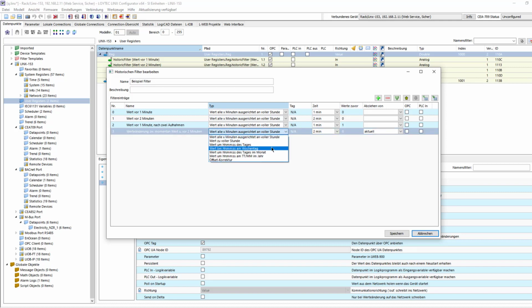Noteworthy is that if one has an energy consumption meter, then one can think of several scenarios when the energy counter could reset or change. For example, when replacing the energy meter with a new one. To accommodate such a scenario, the type offset correction allows entering the old meter's counter in order to provide a continuous capture, as this would offset new filter values of the current meter count so that there are no unexpected gaps or jumps of filter values.